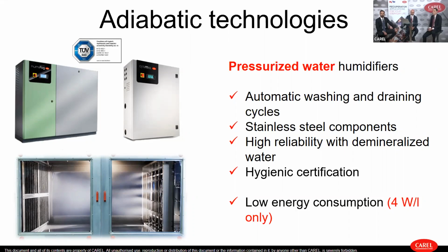It's an interesting point that we have to take into consideration because, as Paolo had already mentioned, the amount of fresh air that we have to introduce inside buildings is increasing due to the requirements given by the COVID norms and so on. Increasing the amount of fresh air during winter means that we have to increase the humidification load. So energy consumption has to be reduced if we want to be energy efficient. Hygienic adiabatic humidification can be at the same time hygienic and efficient.